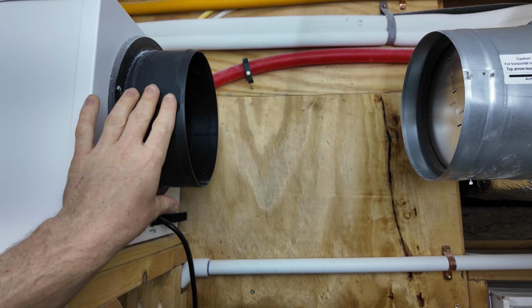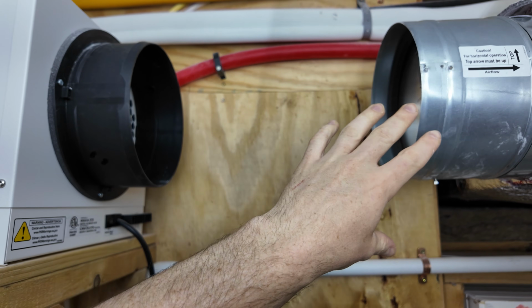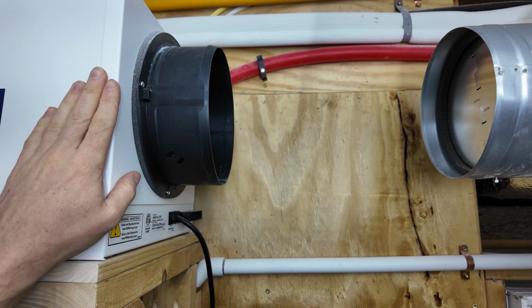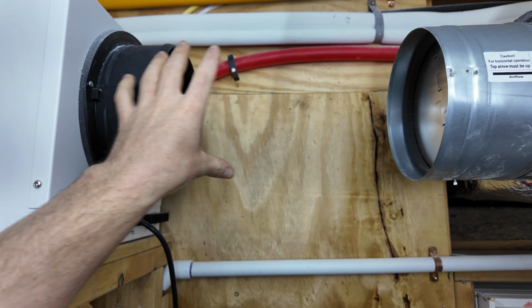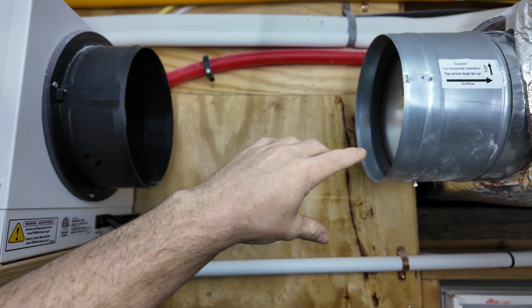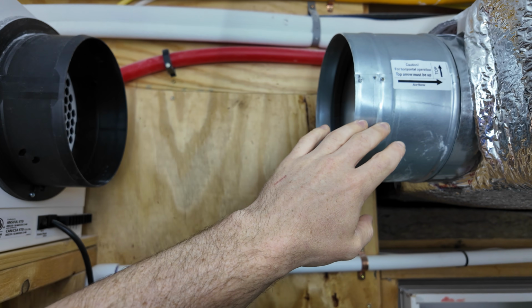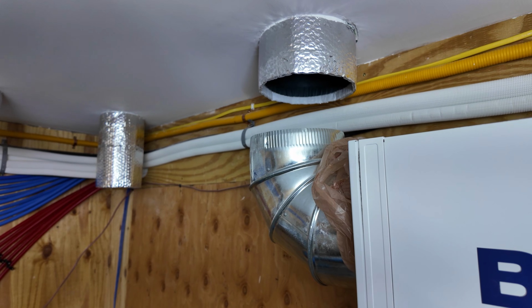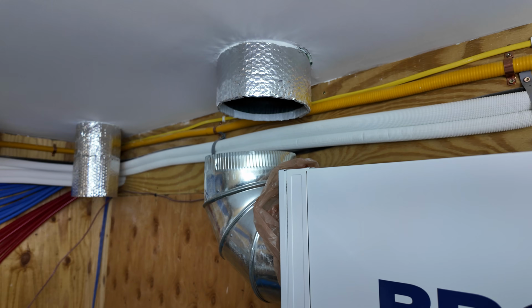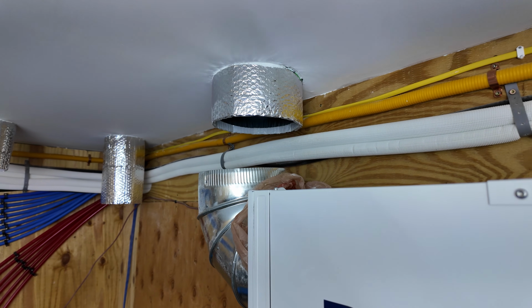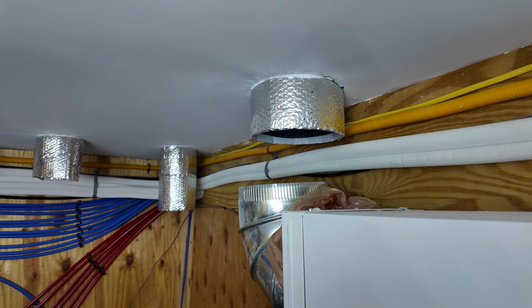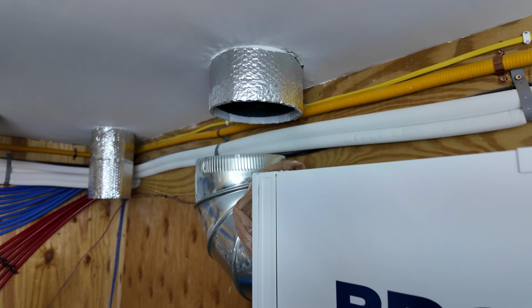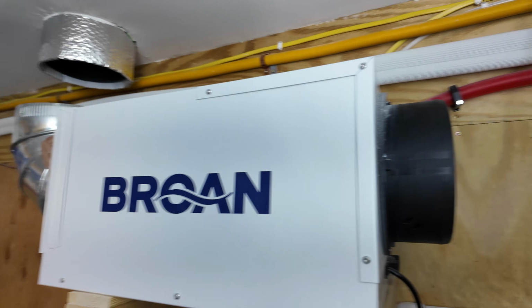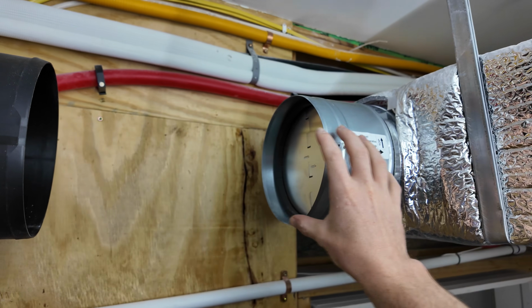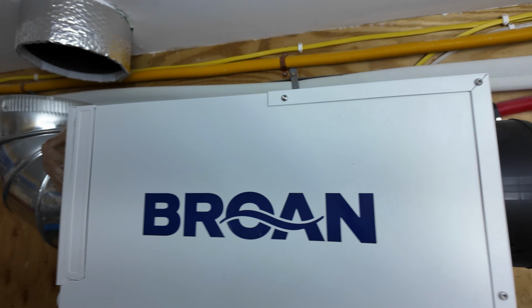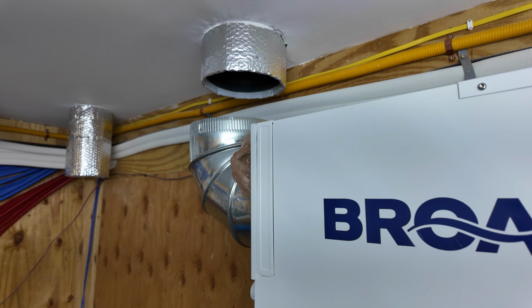It is recommended to put a piece of flex between any rigid ductwork and the unit, because this does cause some vibration, and if this is all rigidly connected, that vibration is more easily transmitted to your rigid ductwork. Same story for this guy up here, just gotta bridge that gap. That's only like 6 to 7 inches probably, so ideally you want 1 foot minimum, that's what the instructions say. But with where this unit had to sit in relation to the supply trunk to make sure this was a straight run, that is as close as I could get with that 90-degree elbow on there as well.